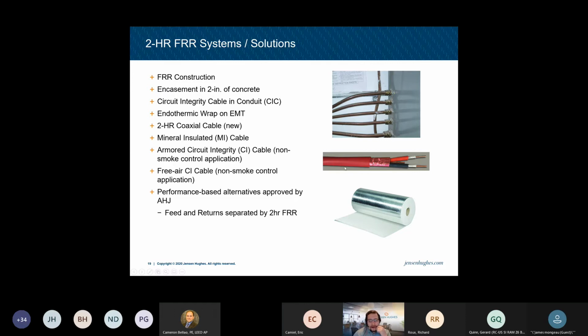So you have basically a fire rated cabling that's listed, a 2 hour listed assembly when installed, and we'll get into that, in accordance with the listing of the product. So it's supported a very specific way. You're using certain manufacturers' tubing and so on and so forth.